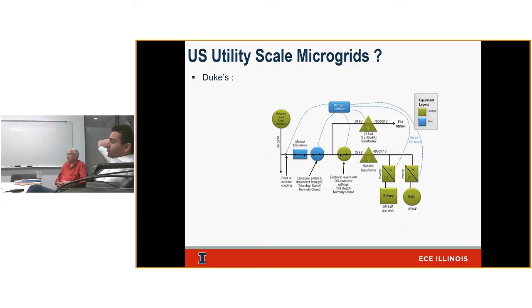This controller is just for secondary control, meaning it looks at the voltage and frequency at the bus and tries to regulate them based on inputs from these assets. Whatever the voltage is, whatever kW and kVAR contribution is coming from the battery and solar, it makes sure the voltage and frequency are regulated on the bus. It's also watching for disturbances, so anytime you lose the grid, it does something depending on the current mode of operation and where it wants to go.